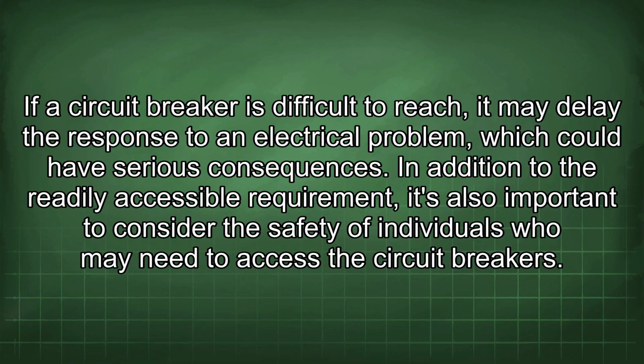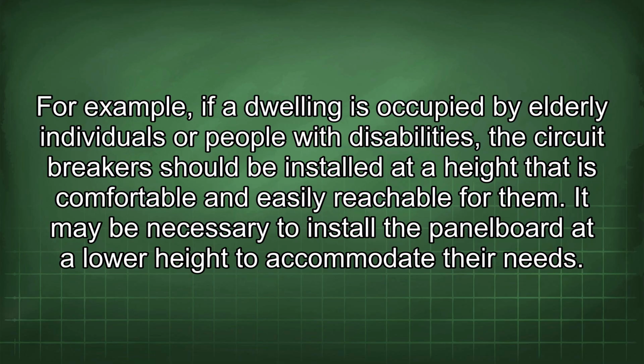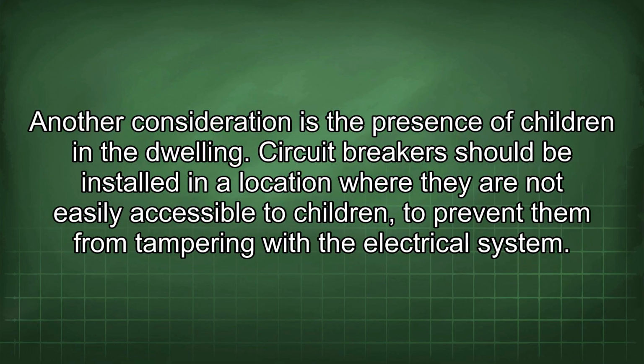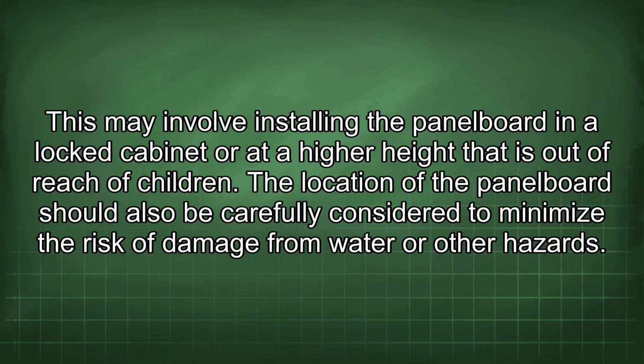In addition to the readily accessible requirement, it's also important to consider the safety of individuals who may need to access the circuit breakers. For example, if a dwelling is occupied by elderly individuals or people with disabilities, the circuit breakers should be installed at a height that is comfortable and easily reachable for them. It may be necessary to install the panelboard at a low height to accommodate their needs. Another consideration is the presence of children in the dwelling. Circuit breakers should be installed in a location where they are not easily accessible to children to prevent them from tampering with the electrical system. This may involve installing the panelboard in a locked cabinet or at a higher height that is out of reach of children.